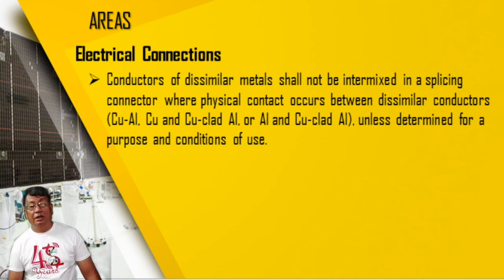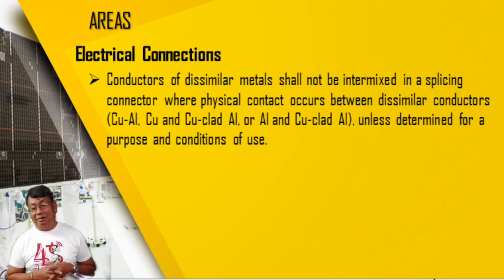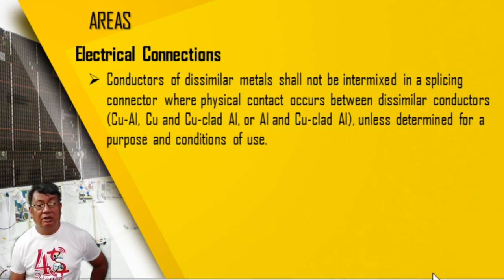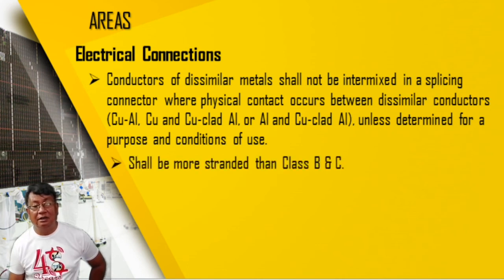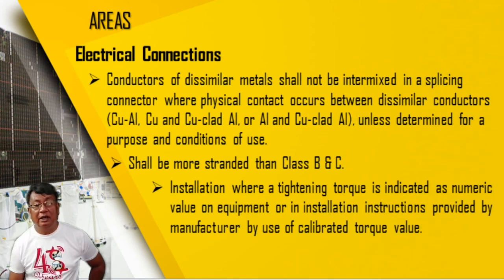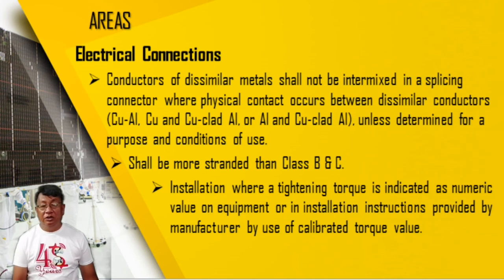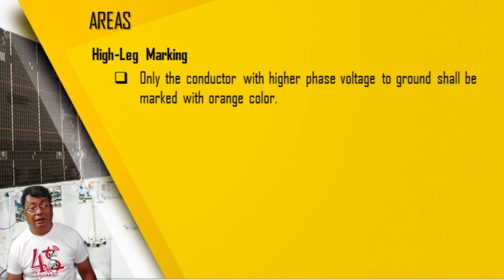So conductors of dissimilar materials shall not be intermixed in a splicing connector where physical contact occurs between the dissimilar conductors. So, for example, some events happen where there is a short circuit because of a copper-aluminum conductor connection, and maybe there is a chemical reaction. Then there is what we call a loose connection, and it will cause a hazard. Okay, so what else? Stranded conductors shall be class B and C. An installation where a tightening torque is indicated as a numeric value on equipment or in the installation instructions. Okay, so we have this high leg marking.